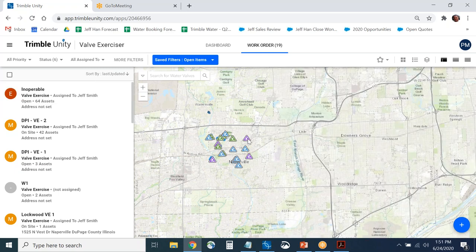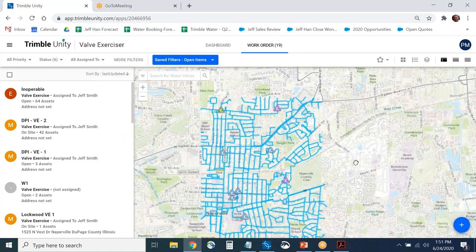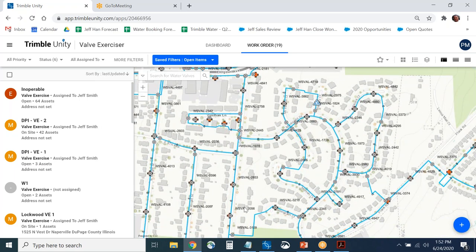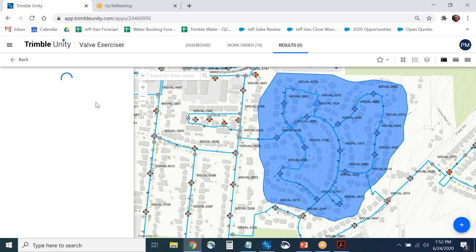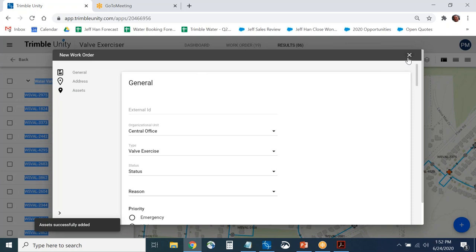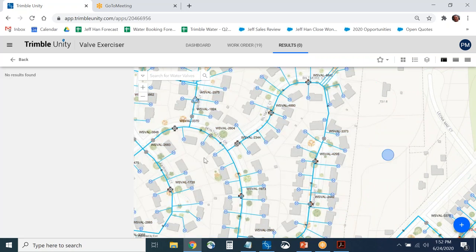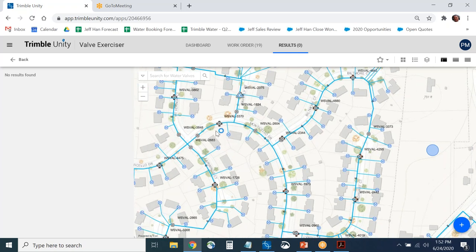Another method for creating a valve inspection is simply using the map. If you're looking at your map and want to select a certain area — say all the valves in a particular neighborhood — you use the selection tool, draw a polygon around it, and create a work order. You can also visually look at all valves colored gray, indicating they haven't been operated during this cycle, and select them ad hoc to create work.